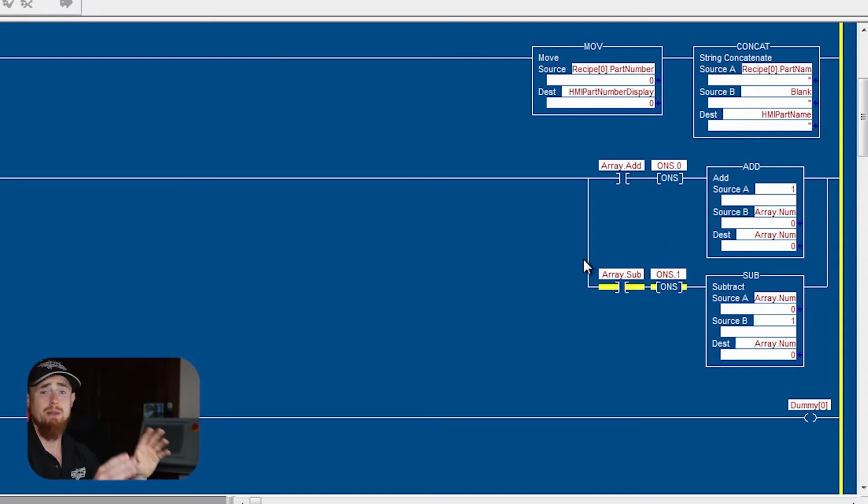Now, this particular video, we didn't put anything in place. If you want us to go further into how to build recipes out, we'll build more of that structure and show you how to limit some of that stuff. But essentially what you would do is you say if it goes above a certain value, you write it to a smaller value. So if it goes above 50, write it to a 50. If it goes below 0, write it to a 0. And those metrics will stop your PLC from going into that fatal state and crashing. You may have to put a buffer between these numbers here too, by the way.